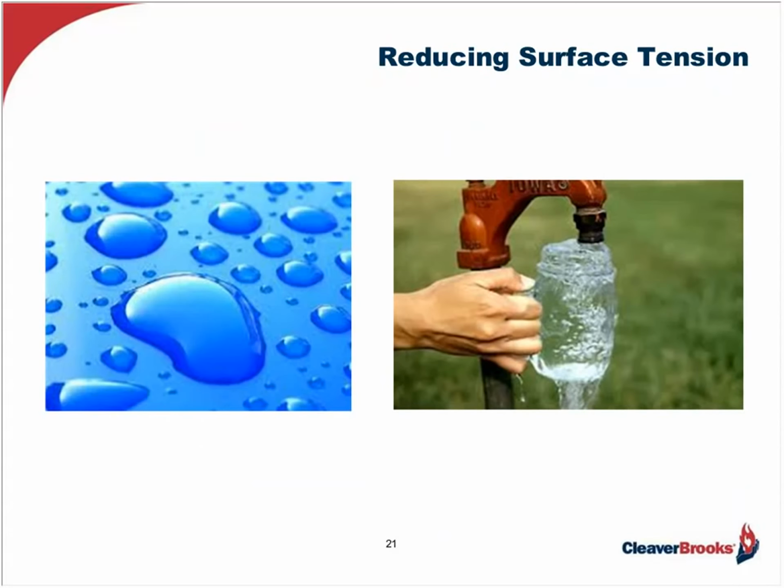All right, so much for the why of deaerator science. Now let's spend the balance of our time looking at the what and how factors. Firstly, we need to understand and appreciate the complexity of water, not only its constituents, but its characteristics. For instance, water possesses a high degree of surface tension, which tenaciously holds things in place unless a surfactant is applied or some other means are imposed on the water to reduce the tension, and that's exactly what deaeration does.